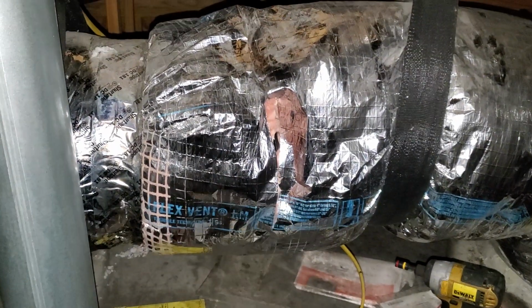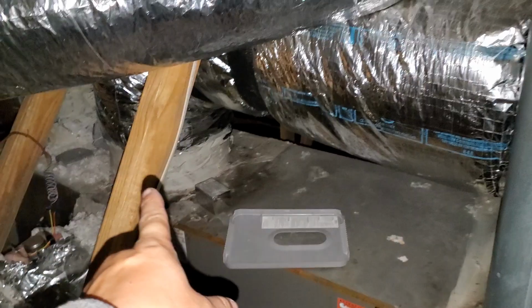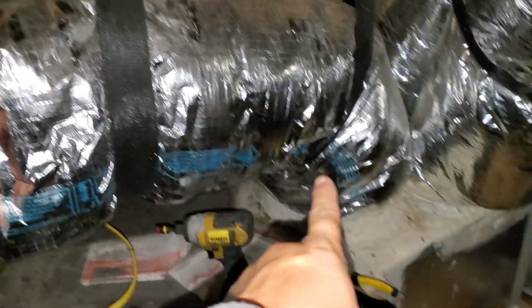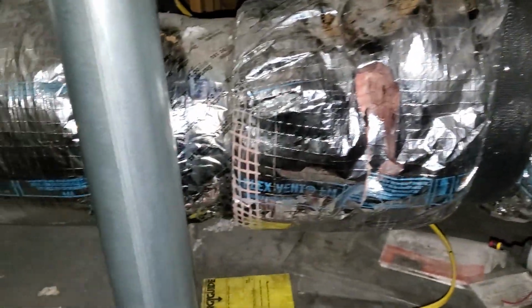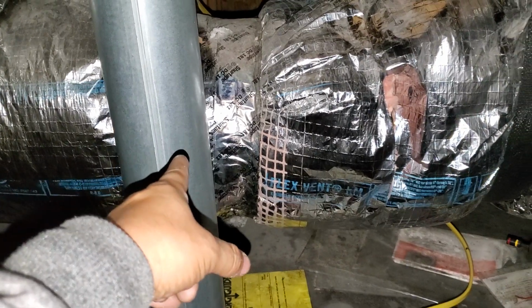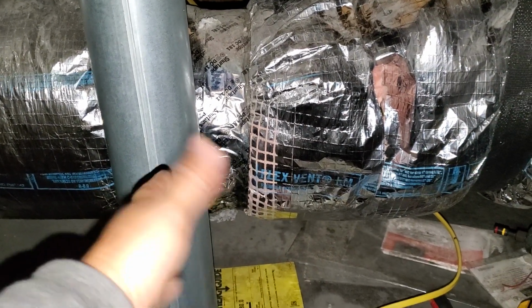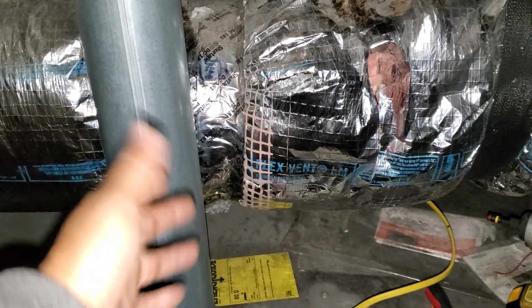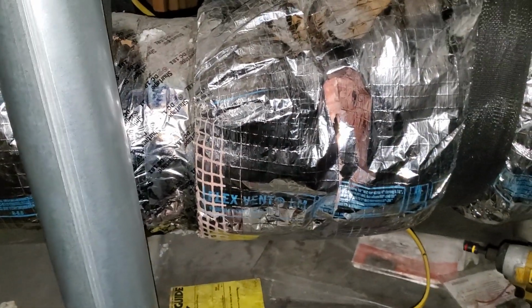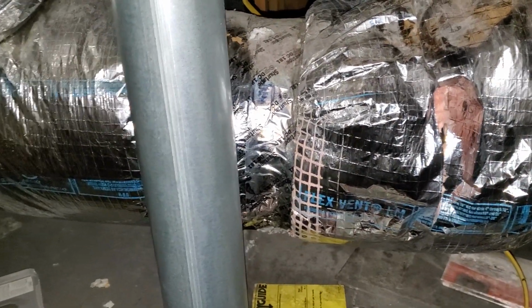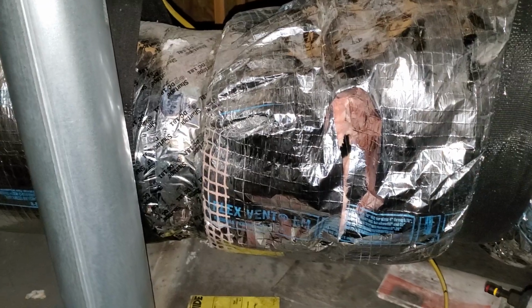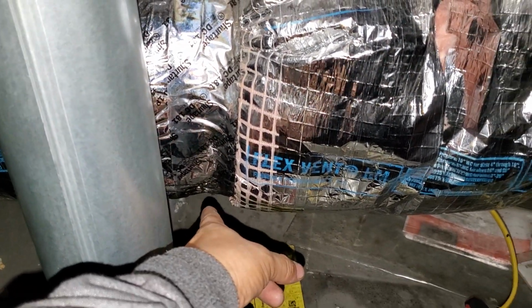You can see I got a hole cut in this terribly installed 12-inch bypass. But the bypass damper is right behind the flue. There's no handle on the bypass, so anytime the fan would come on, the bypass would just do whatever it wanted to do. There's no counterweight, it's not a static bypass or anything. So what I did for testing purposes is I drove a screw in, closing that bypass damper so I wasn't recirculating.